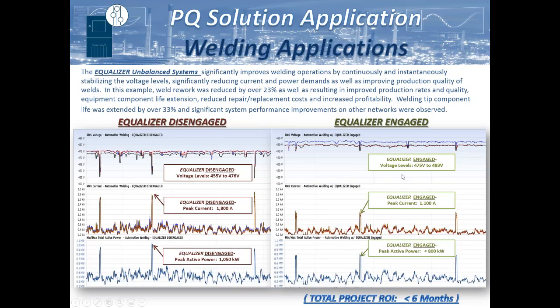Welding is another really good application for us. As I was saying before, we have unbalanced systems that can treat each individual phase separately. You can see here with the system disengaged versus engaged, we've raised the voltage levels by about 5. But whenever the welding processes are being initiated, you can see this peak current here of 1,800 amps. We've reduced that down to 1,100, and these voltage swings, instead of having a 20-volt voltage differential, now we're talking about 5 volts.